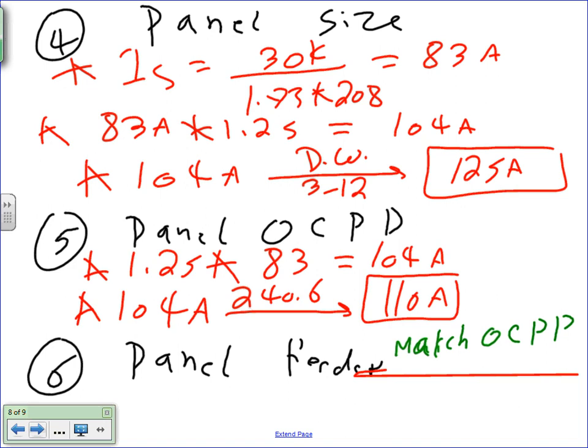Now here's my question. You go to a company and you find that they actually size it 100. They put this one 125 to match the panel, and they size the cable 125 amp. That's okay, as long as they size the cable to match the overcurrent protection device. So can I make this one 125? Yep. But I have to make the panel match it now, and the conductor match it. Okay.